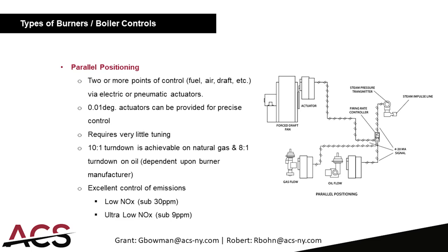The next step up is a parallel positioning system, where each point of control has its own servo motor or actuator — either electric or pneumatic. Typically very accurate servos are used for precise control. The CPU memorizes an f(x) curve for each control point. You can get a 10-to-1 turndown on natural gas and an 8-to-1 turndown on oil, depending on the burner manufacturer. This is an excellent choice for emissions control, for low NOx burners sub-30 PPM and ultra-low NOx burners.